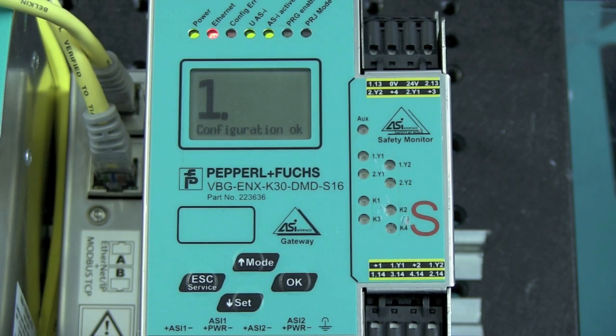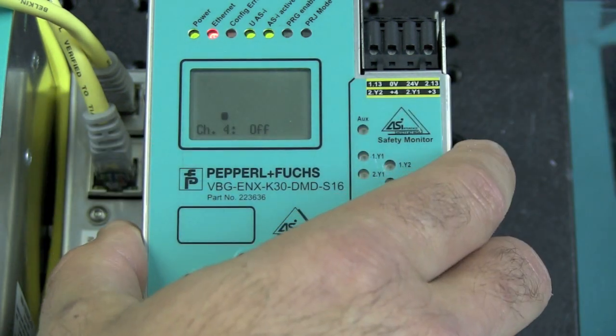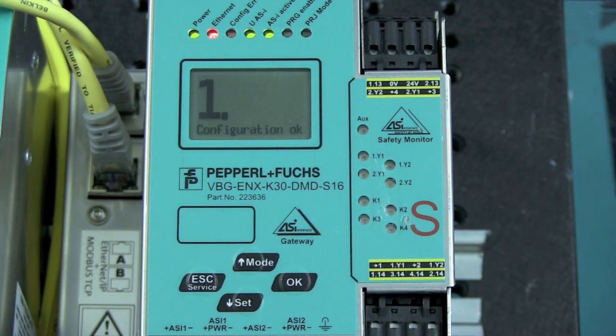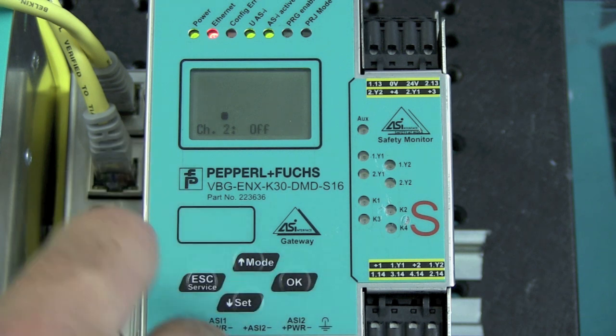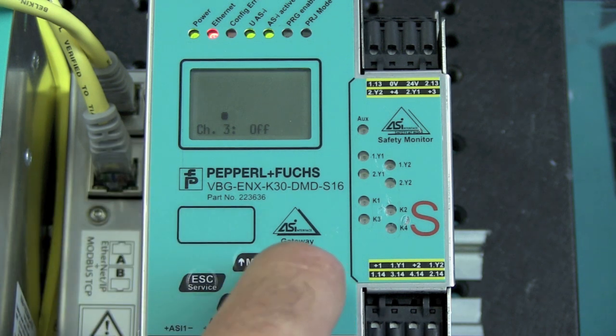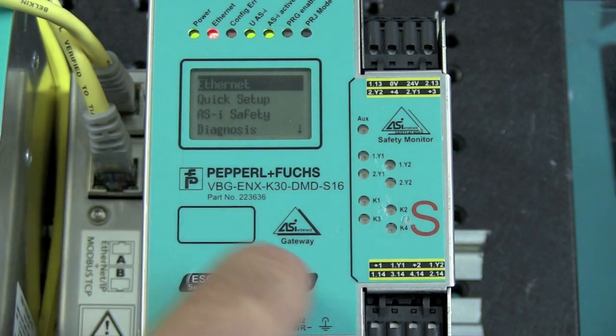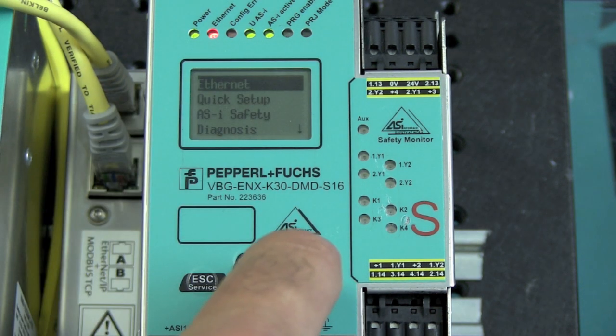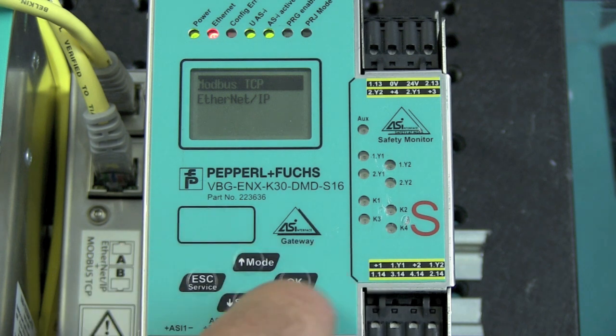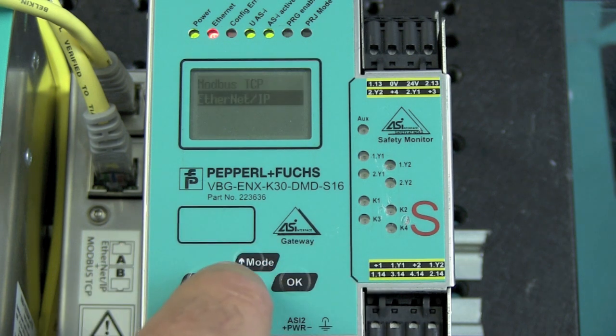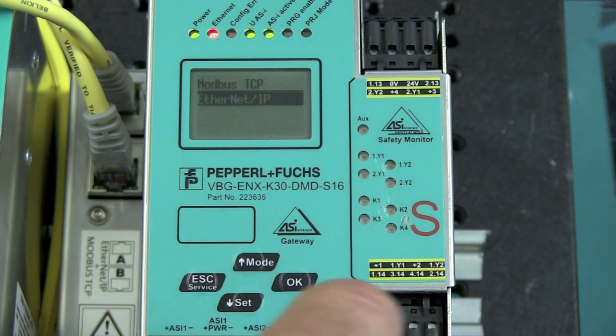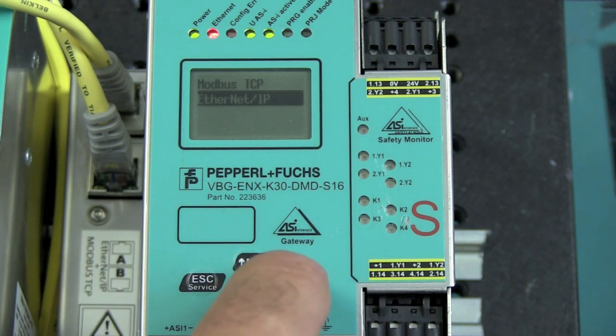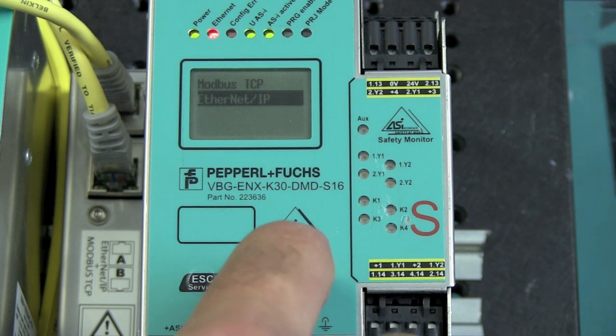Okay, now I want to show you how to configure the IP address and the network settings directly in the AS interface gateway. So, the first thing I want to do is enter the menu by hitting OK. Go into Ethernet, because that's what I want to configure. You get two protocol options, Ethernet IP and Modbus TCP. Allen-Bradley uses Ethernet IP, so that's the one I want to choose.